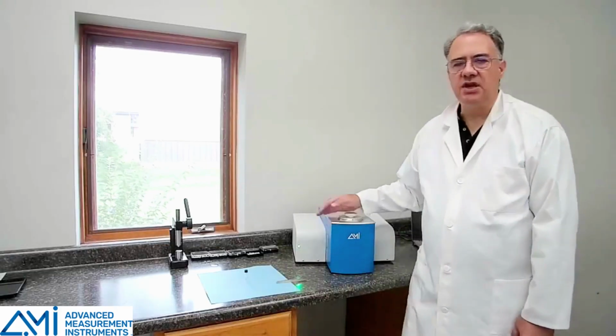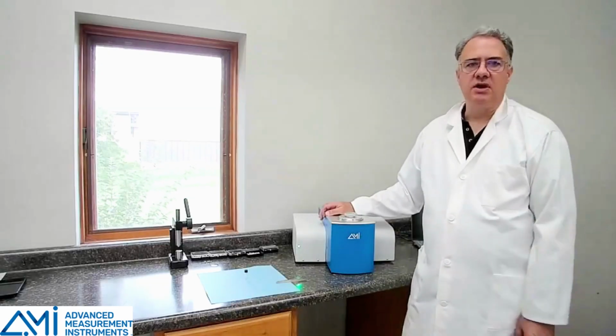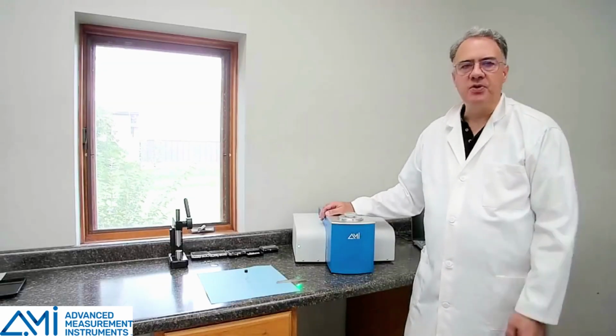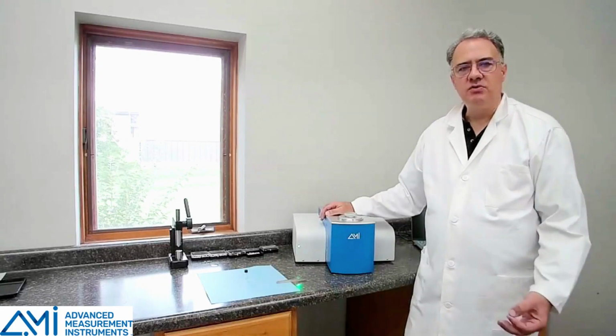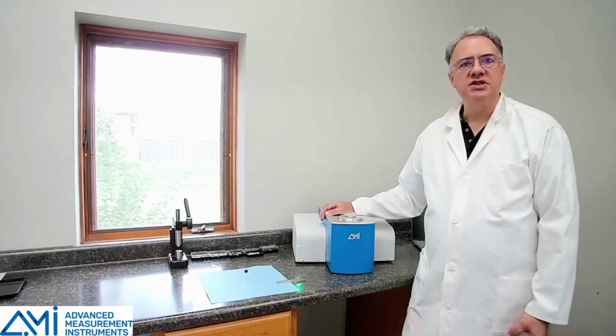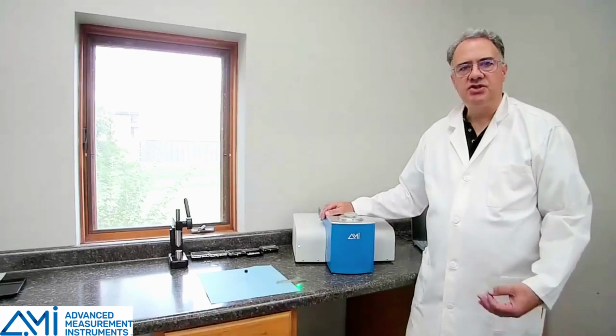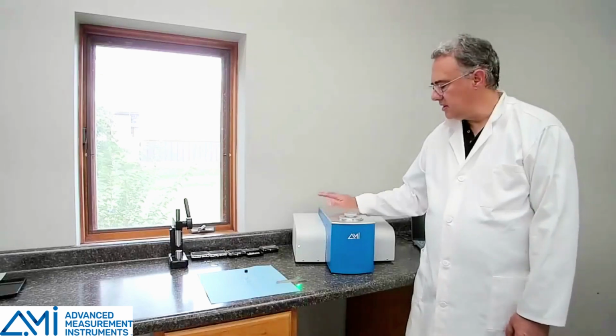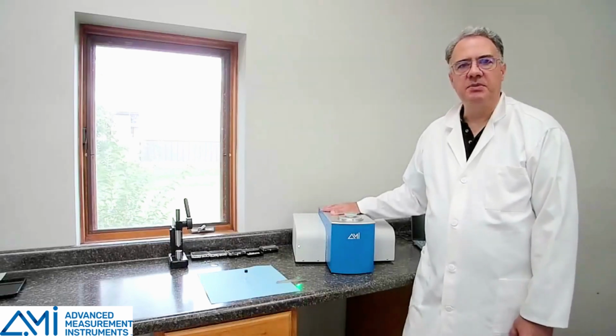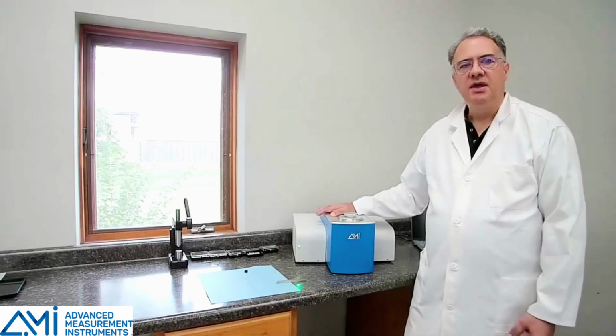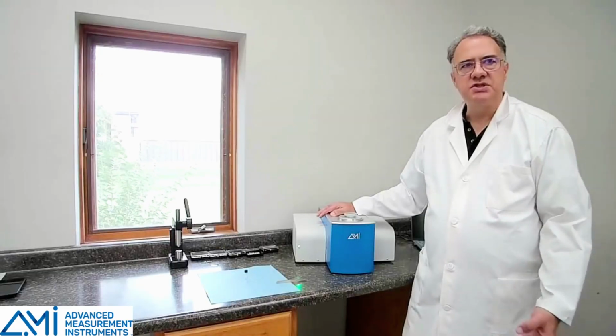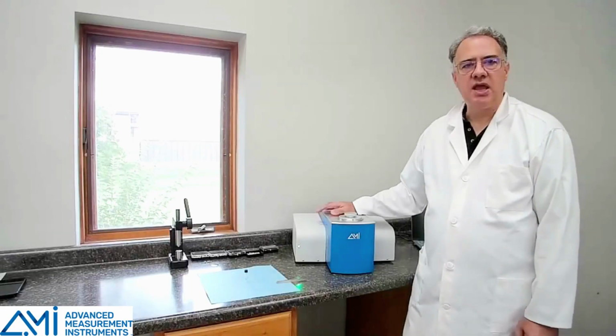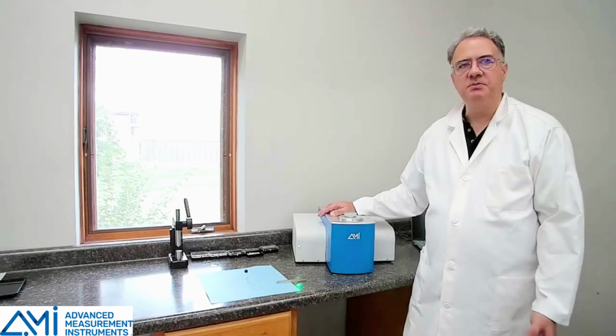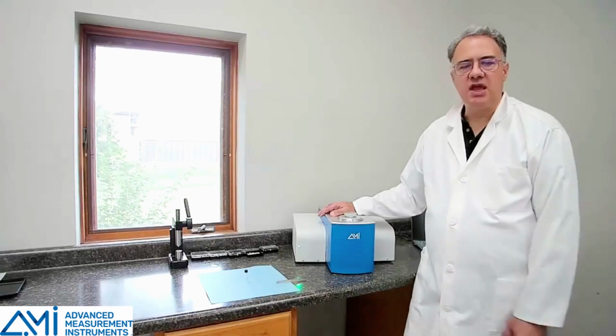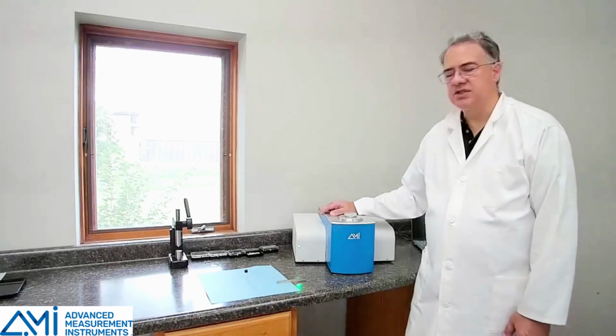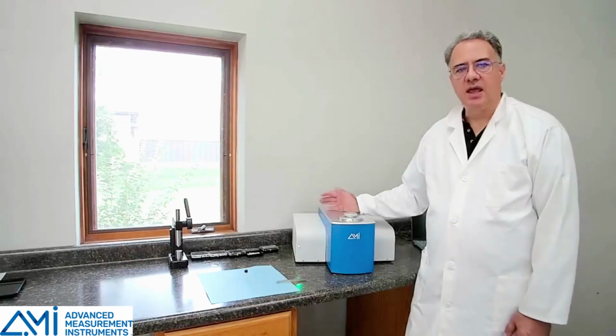The importance of calibration is that you want your data to be the most accurate it can be. They come pre-calibrated from the factory, but when you receive them, it's a good idea to run a calibration test to make sure that they haven't changed during shipment. The main cause of change in an instrument is over long periods of time, the capacitors, resistors, and other components can change slightly. They're still within specification, but because of the change in the makeup of the components, you will get a slight change in the calibration.